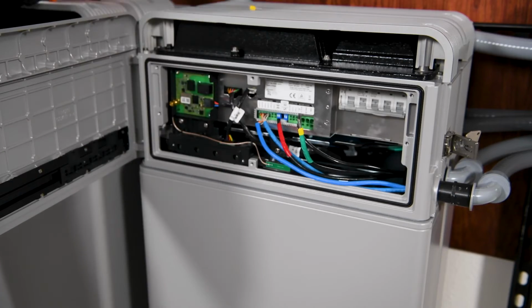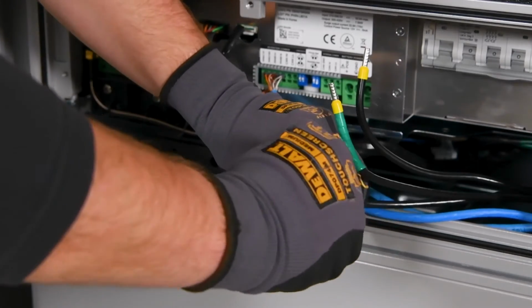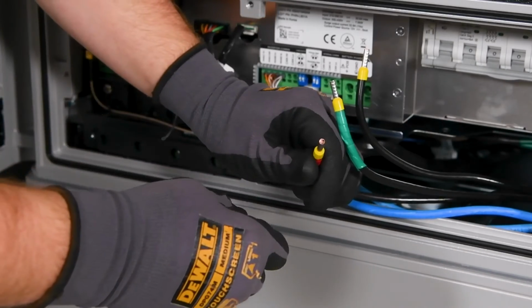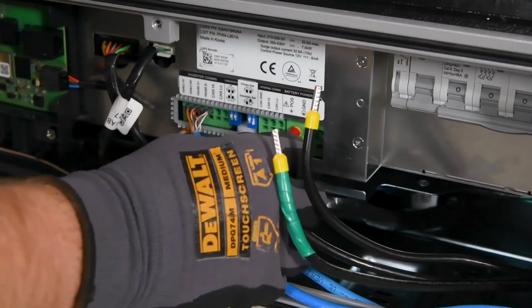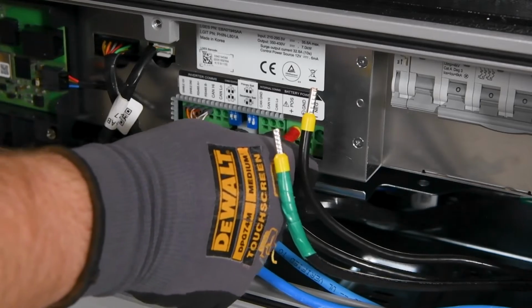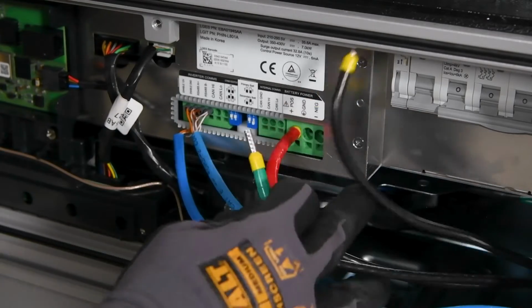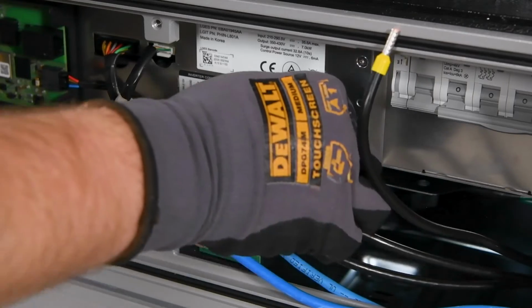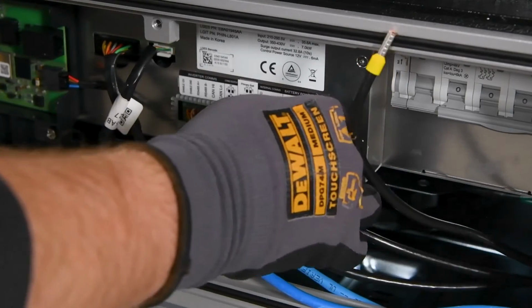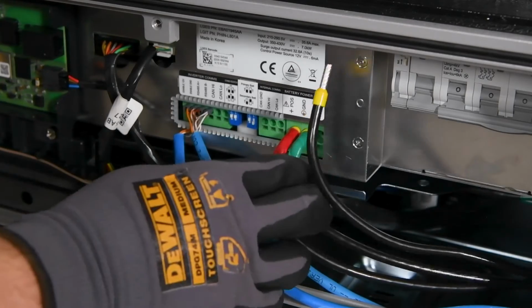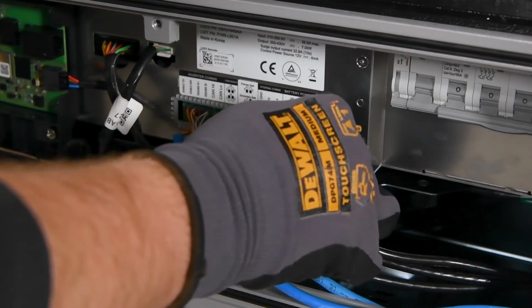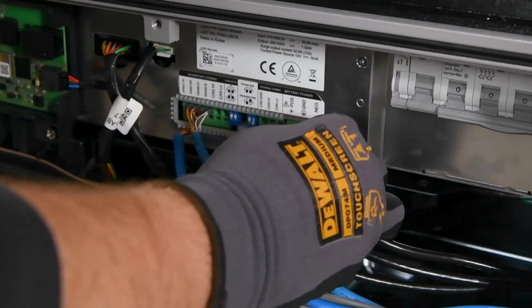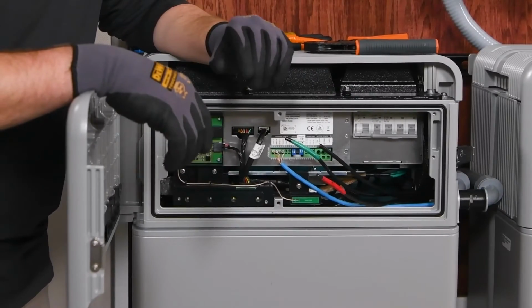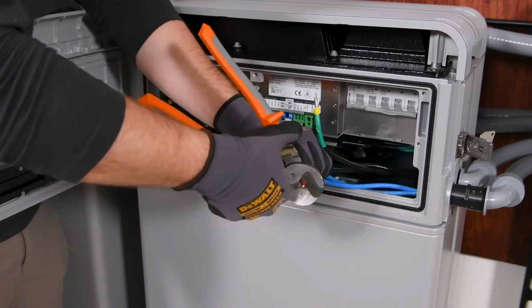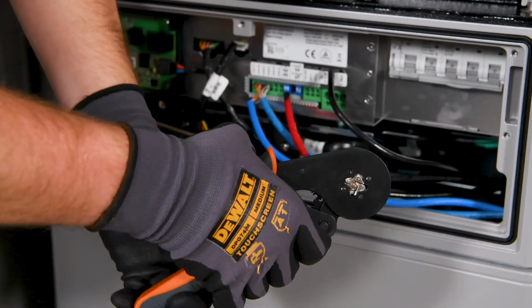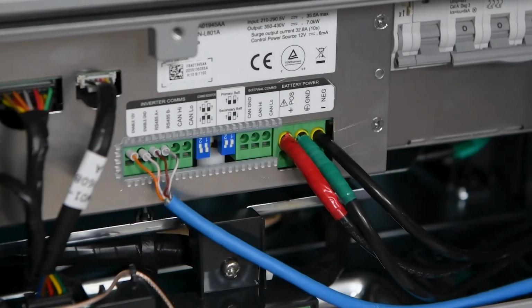With our conductors ferruled, we'll go ahead and insert them into the terminal block here. We'll take our red, connect it to positive. Again, we're just pushing in, and giving it a light pull to make sure that the teeth on the back bite into the ferrule. We'll take our ground and connect it to GND, or ground. And our negative. We'll repeat the same steps for the primary battery that we did with the secondary. We will remove the insulation, insert our ferrules, and insert them into the terminal block here.